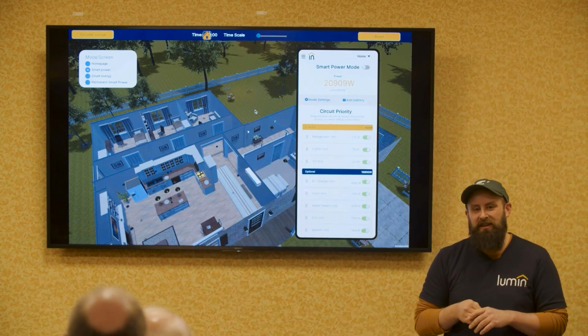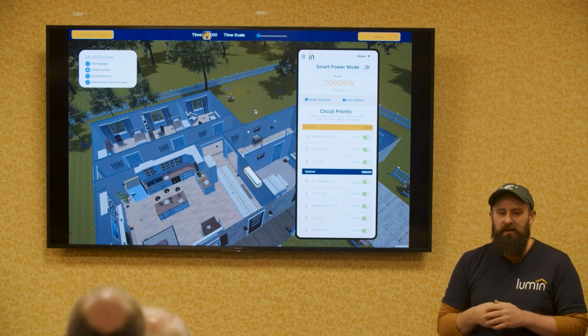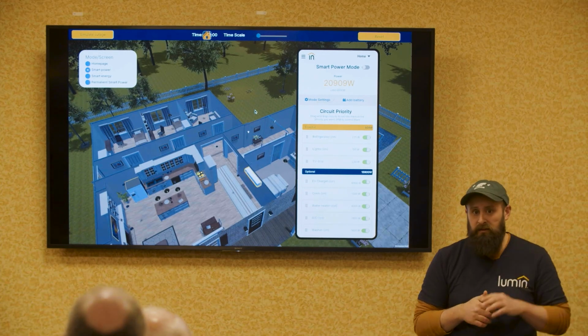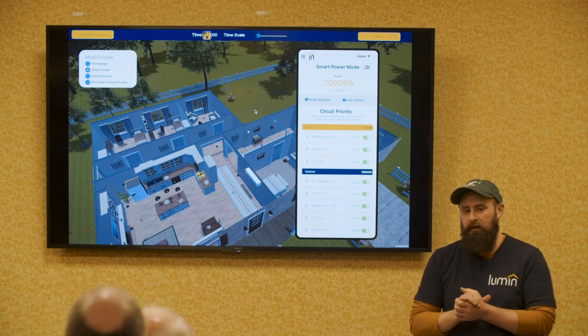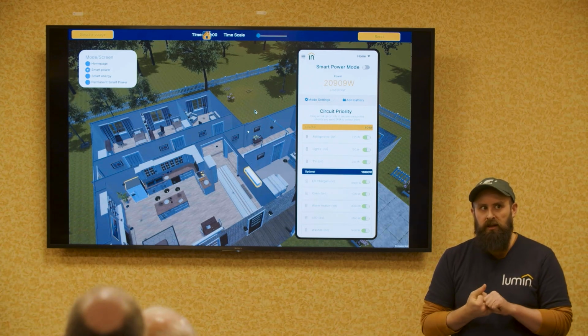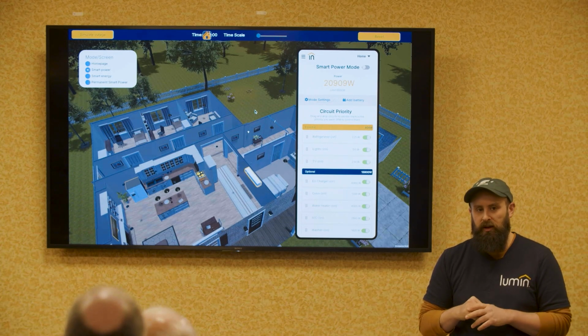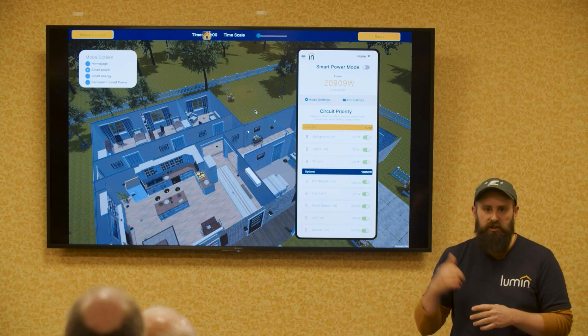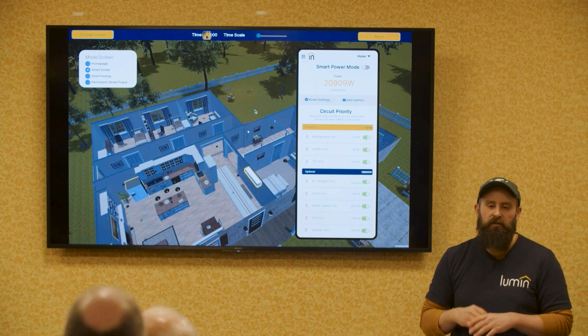How is it powered? Where does it land? So it's a 15 or 20 amp dual pole breaker landed in whichever service panel is being powered, or whichever load center is being powered.